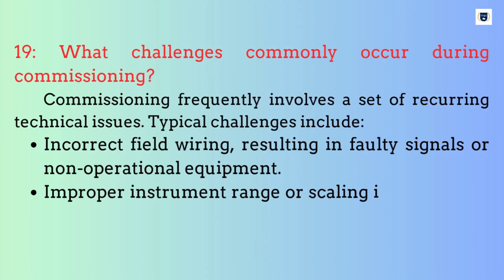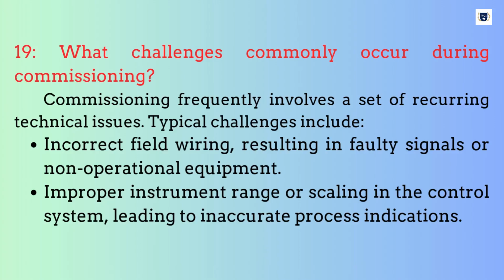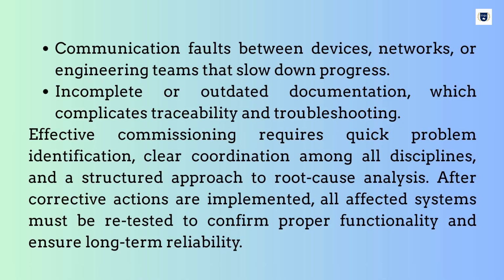What challenges commonly occur during commissioning? Commissioning frequently involves a set of recurring technical issues. Typical challenges include incorrect field wiring, resulting in faulty signals or non-operational equipment, improper instrument range or scaling in the control system, leading to inaccurate process indications, communication faults between devices, networks, or engineering teams that slow down progress, incomplete or outdated documentation, which complicates traceability and troubleshooting.